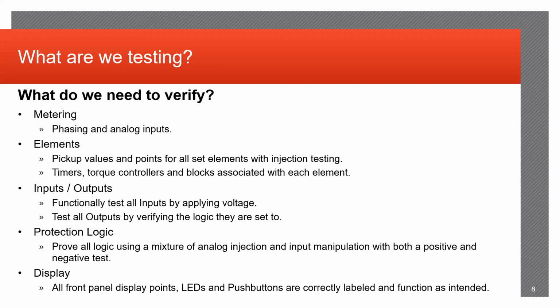Any inputs and outputs associated with the relay, usually this will be any trip outputs, alarms, incoming DC signals from other pieces of equipment like other relays or lockouts specifically. We're going to be functionally testing all those by applying voltages and currents to correctly identify that they will operate when need be per design intent. As well as protection logic, kind of the same idea, providing injection current and voltages to correctly identify the relay is going to operate when need be based on the protection logic, and as well as displays such as the LEDs, push buttons, all correctly labeled and function as intended.